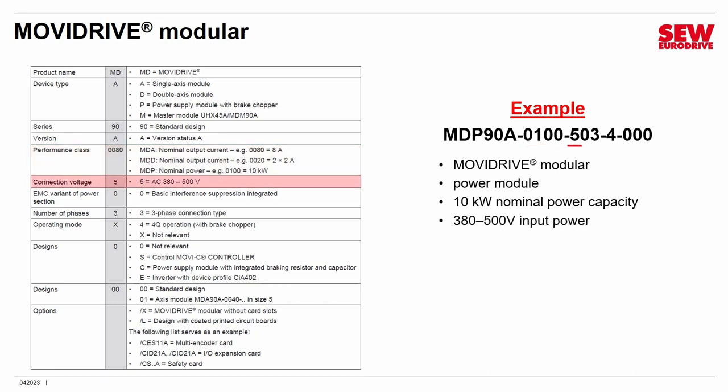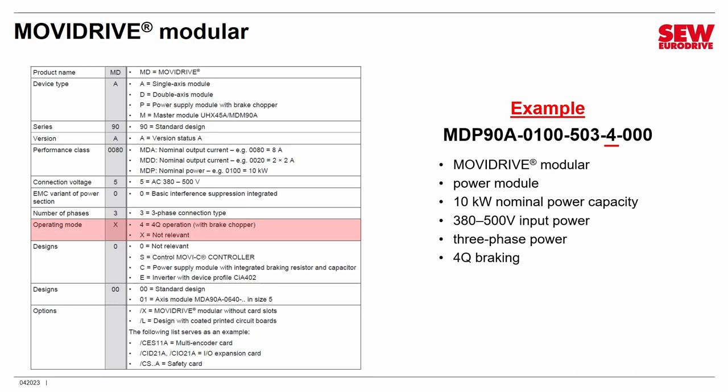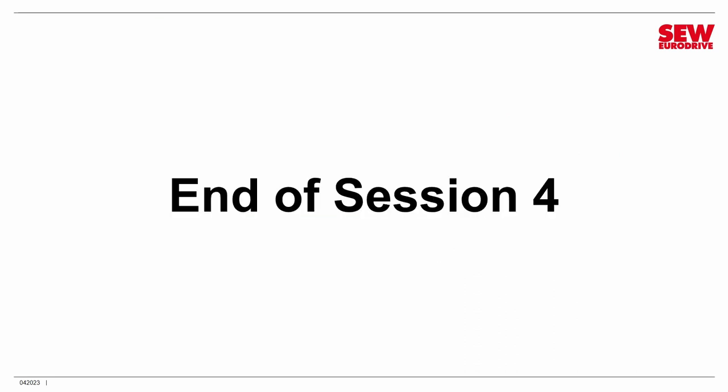The 5 indicates operation on 380 to 500 volts — so probably 460 to 480. Note that we do not make a lower-voltage power supply module at this time; support for 230 to 240 volts is only for MoviDrive Technology and MoviDrive System. These only come in three-phase form. The 4 means you can connect this to a brake resistor — this is where regenerative energy gets handled for MoviDrive Modular; all axis modules feed their regenerative energy back to the power supply, and the brake resistor turns it into heat.